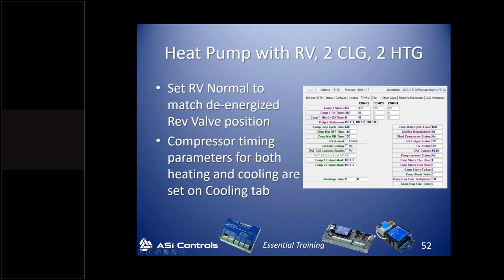Switching over to heat pump, I want to get out of the discharge or economizer case because in our live class it'll be disabled. I found that when left in discharge or economizer mode, I'd use the heat pump to cool and there'd be a delay because it was trying to use the economizer. Since we don't have a valid outside air reading, economizer operation is disabled. I want to change the personality to heat pump with reversing valve.